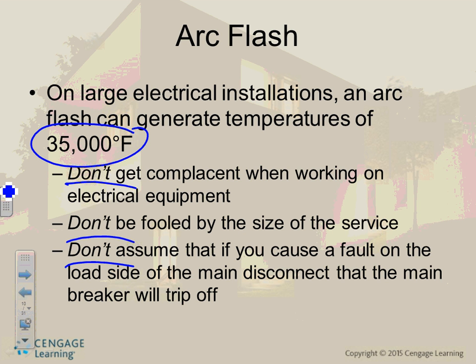A couple of assumptions people make: disconnect the load side of the main, assume the main breaker will trip. There's a lot of assumption, guys. For example, people assume the green conductor is always grounded and not hot, but you never know who wired it. I treat every conductor as energized until proven otherwise.